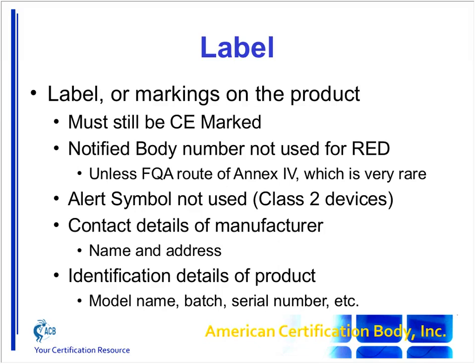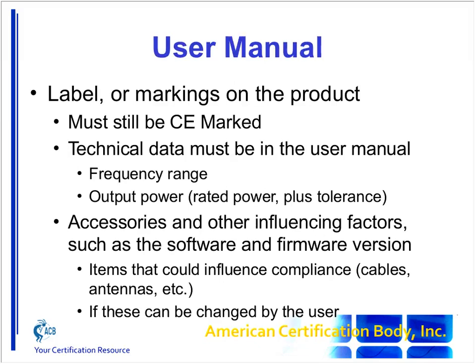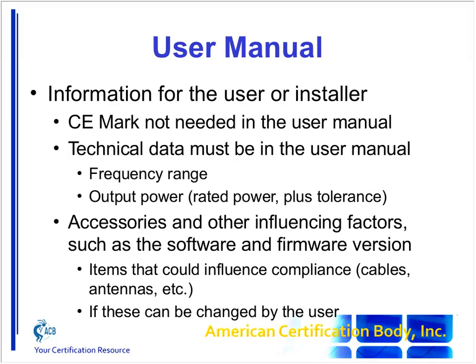For the user manual: under the RED, the CE mark does not need to be in the user manual, though it did under the R&TTE. Here's a new thing: the technical data of the product must be in the user manual. It must state the frequency range of the product and also the rated output power of the transmitter.